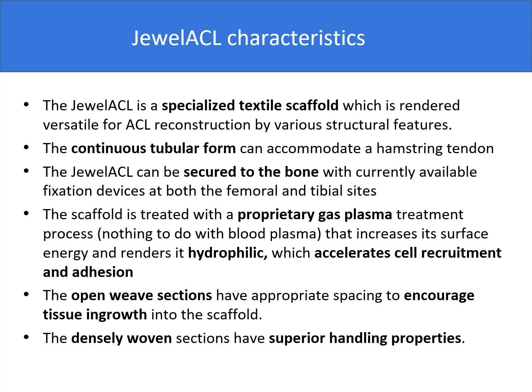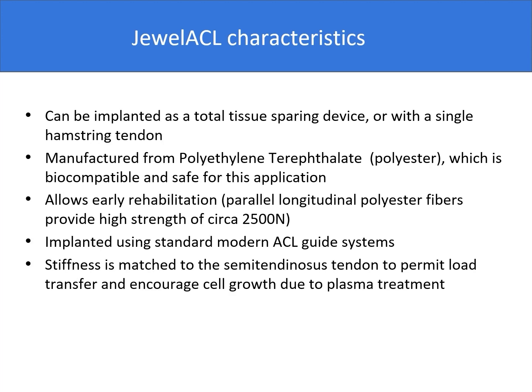Its continuous tubular form can accommodate a hamstring tendon. The JewelACL can be secured to the bone with currently available fixation devices at both the femoral and tibial sites. The scaffold is treated with a proprietary gas plasma treatment process that increases its surface energy and renders it hydrophilic, which accelerates the recruitment and adhesion. The open weave section has appropriate spacing to encourage tissue ingrowth, and the densely woven section has superior handling properties.